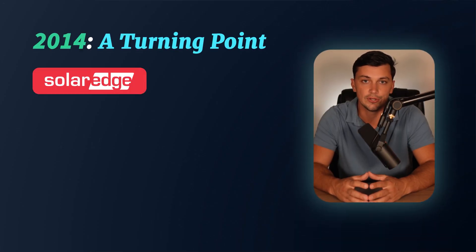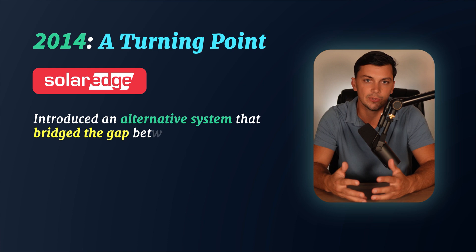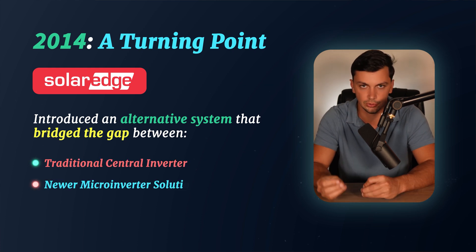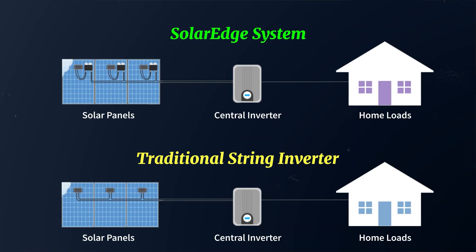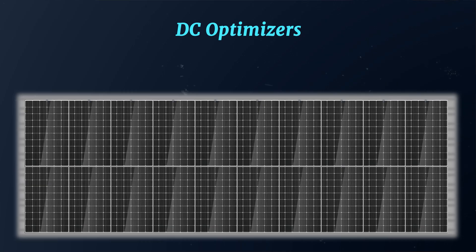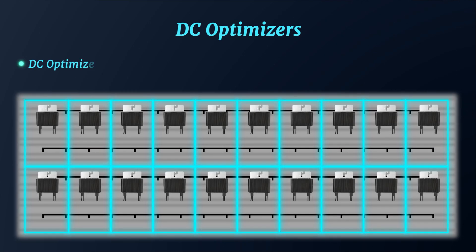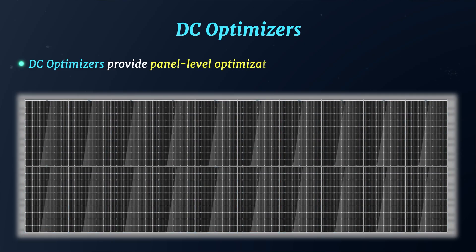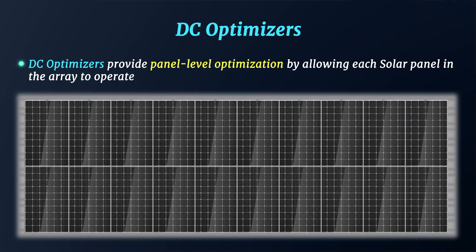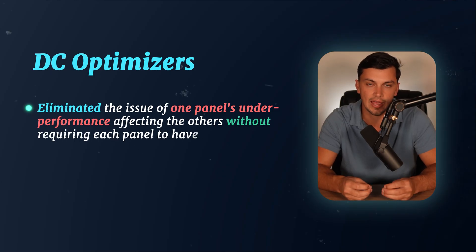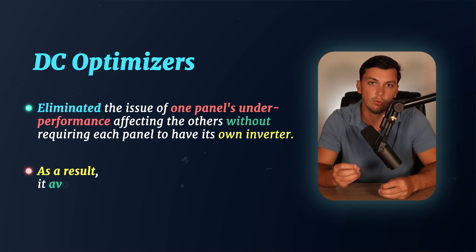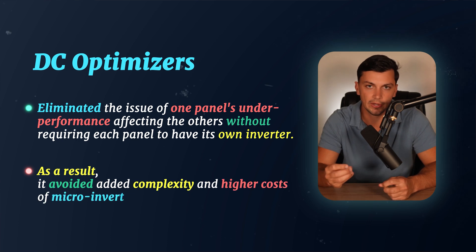In 2014, a company called SolarEdge introduced an alternative system that bridged the gap between the traditional central inverter and the newer microinverter solution. This system is now known as the DC-optimized inverter solution. The SolarEdge system retained the simplicity of wiring and installation found in a traditional string inverter, but added a new component — optimizers. These devices are installed behind each individual panel and provide panel-level optimization by allowing each solar panel in the array to operate at its maximum power point, MPP, independently. This innovation eliminated the issue of one panel's underperformance affecting the others without requiring each panel to have its own inverter, avoiding the added complexity and higher costs associated with microinverter installations.